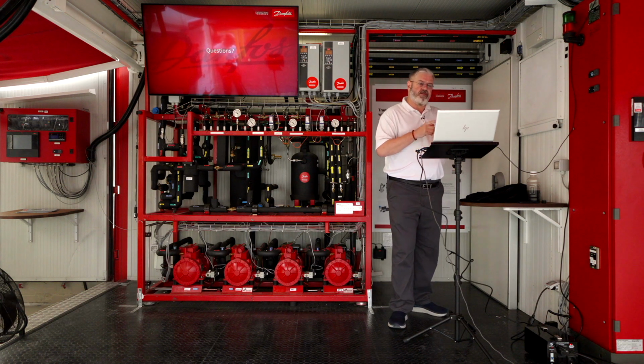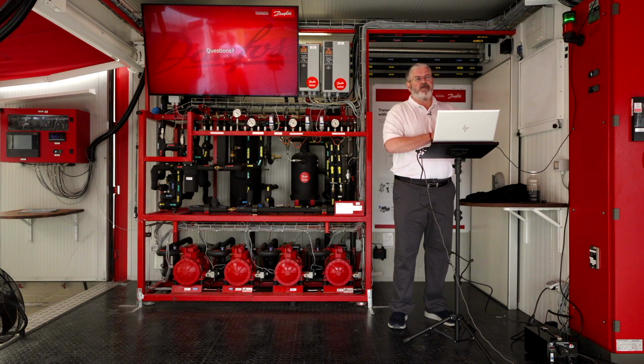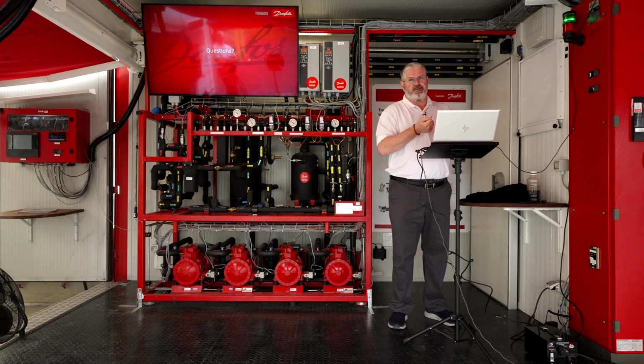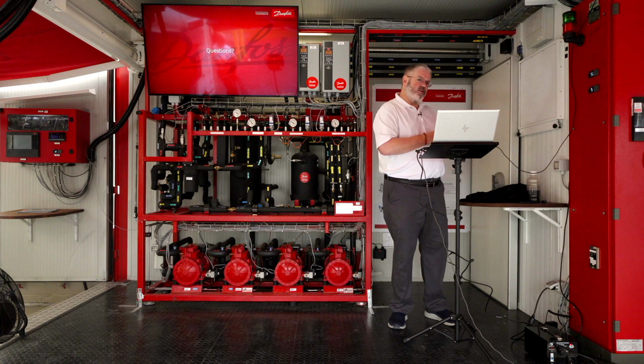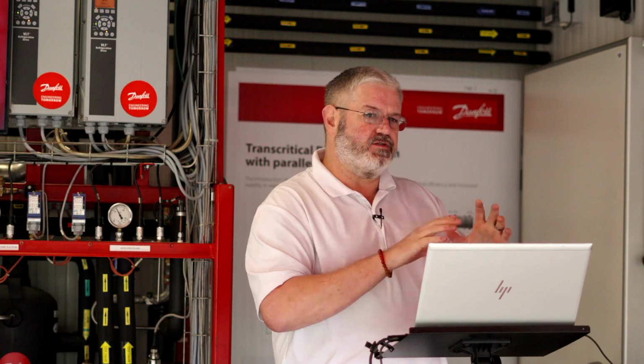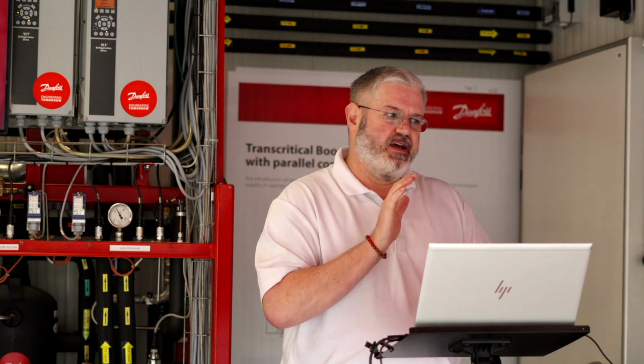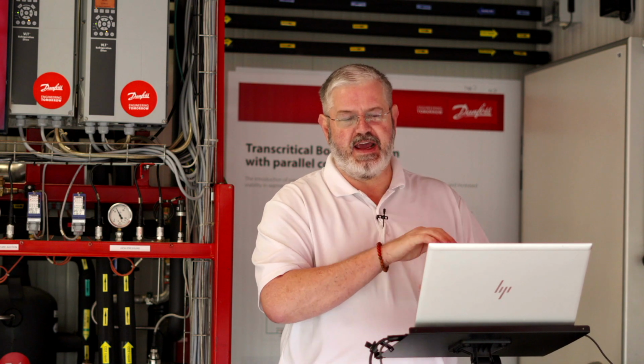Temperature control, I think I caused confusion earlier when I mentioned we have a shelf to put gas cooler discharge heat into the box. We do that to get the system to run. If we want to keep compressors running during a presentation, we slide that open. So we kind of use this for load control. But with CO₂ in general, a transcritical system, think of your walk-ins and your cases the same way you operate with HFC. You're just going to have an electronic expansion valve instead of a mechanical expansion valve, and a case controller per case.